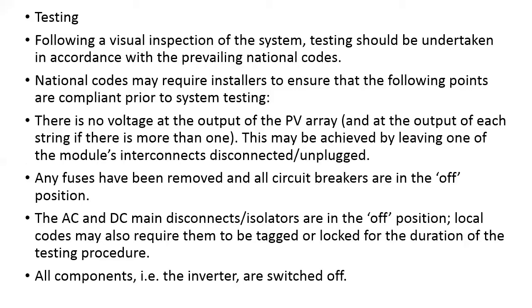Once it has been installed and all this checking and monitoring has been done, the next thing we have to discuss is of course the testing. We have to test each and every component, starting from your PV arrays or PV modules, then the combiner boxes, from the combiner boxes to the junction boxes or isolators, from the isolators to the inverters, from the inverters to the metering boxes. All these things have to be tested. This testing has to take place before what we call the handing over to the customer.